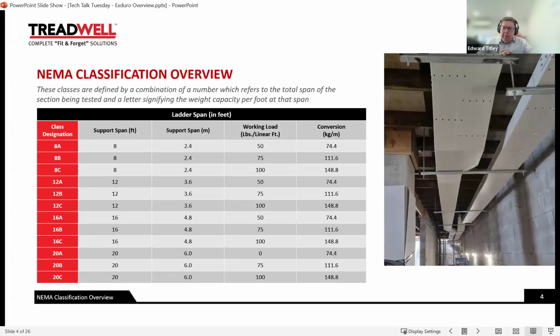Now, a brief look at the NEMA classification. Any cable ladder product, whether it's steel, FRP, aluminium, anything else, is going to have a NEMA classification. Some manufacturers have their own proprietary rating system, like 1, 2, 3, etc. However, they will all convert to a NEMA class designation like we see here. A NEMA class is a number followed by a letter. What that number means is the support span in feet. This little table here, we convert it to meters. So NEMA class 8, 2.4 meter span, 12, 3.6 meter span, 16, 4.8 meter span, and 20, 6 meter span.